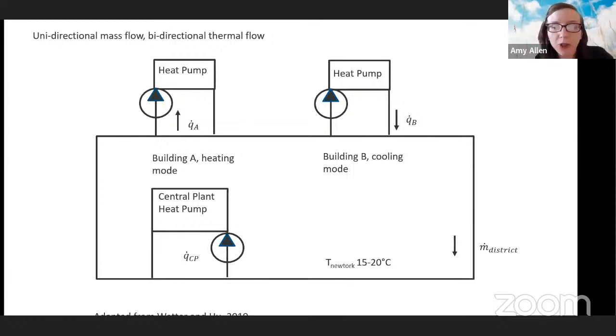And the network temperature in this case can float in a similar range of 15 to 25 degrees C or so. And this network configuration does result in penalties in terms of exergy destruction and thus also higher energy use through the lack of separation of heating and cooling loads, in that buildings are both rejecting and drawing heat from the same side of this loop, so to speak, since it operates with a single pipe.